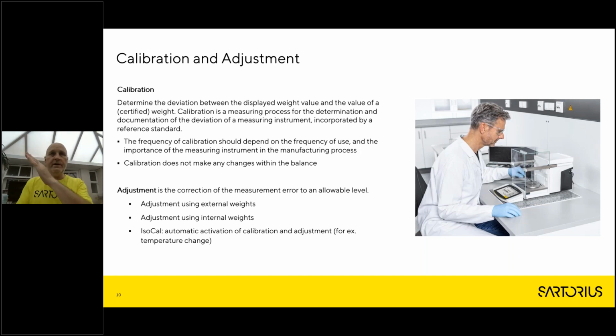We want that slope to be from 0 to maximum. And then once we determine that calibration error, we then adjust the balance. So that's the difference between calibration and adjustment. Adjustment we can do using external weights, which are traceable. We can also do it using the internal weights on the balance. Many balances nowadays have internal calibration facilities, which are triggered either by temperature or time. On Sartorius Cubis 2 and other balances within the Sartorius range, we have ISOCAL, which is our automatic calibration and adjustment, triggered by temperature and time.